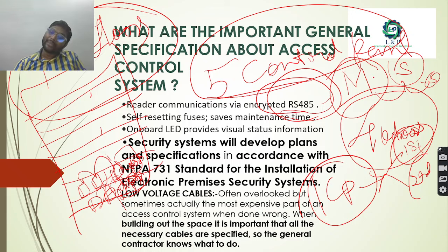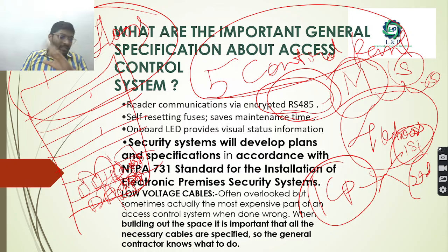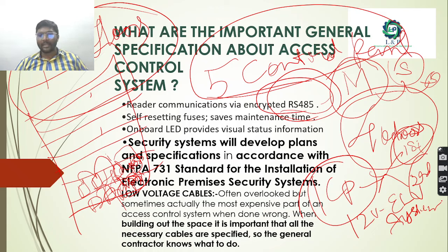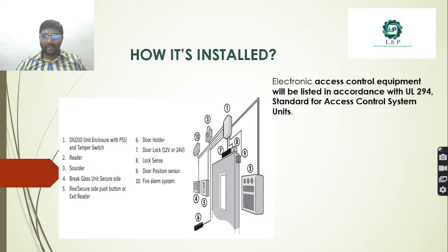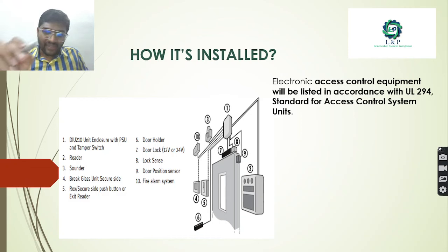Since these equipment use 12 volt supply, they fall under the ELV — Extra Low Voltage — category. Electronic access control equipment should always be installed in accordance with UL 294 standard — the Access Control System Units standard.